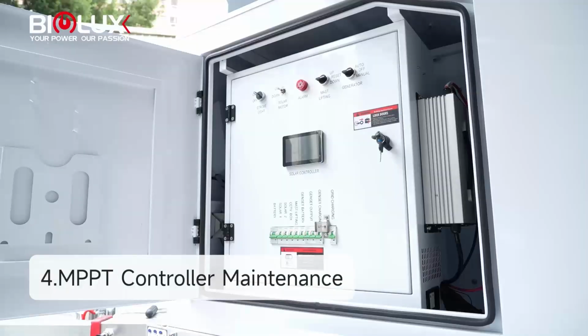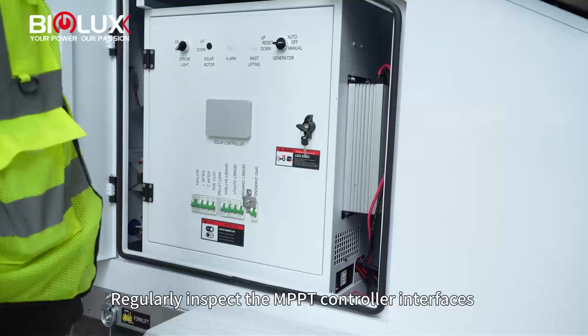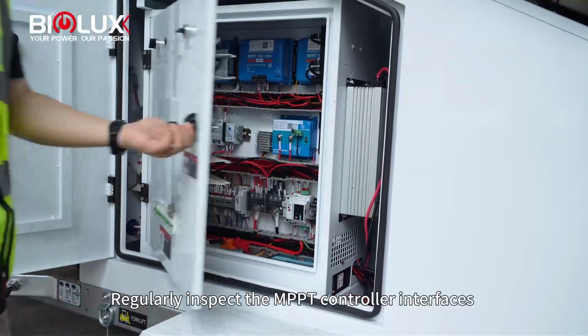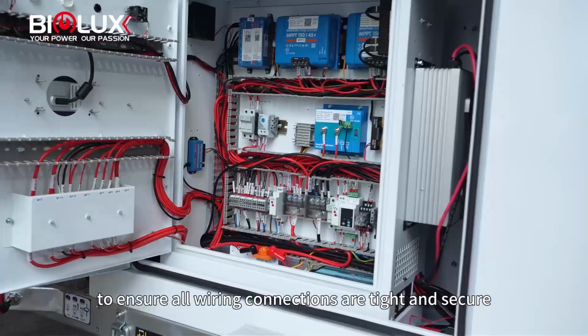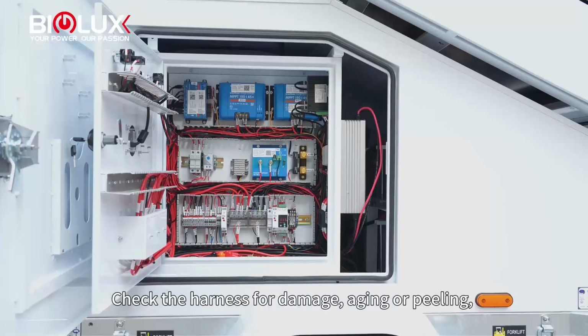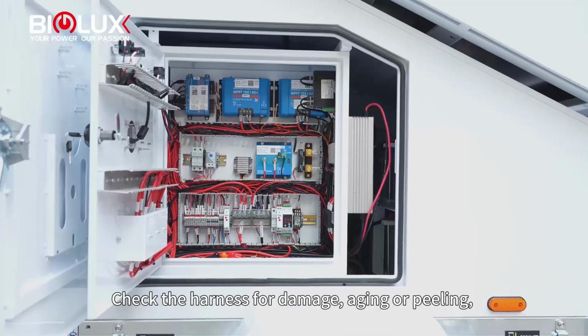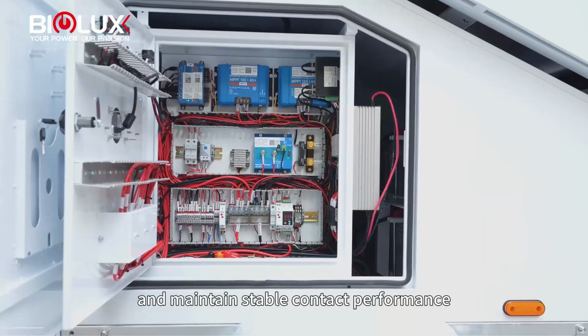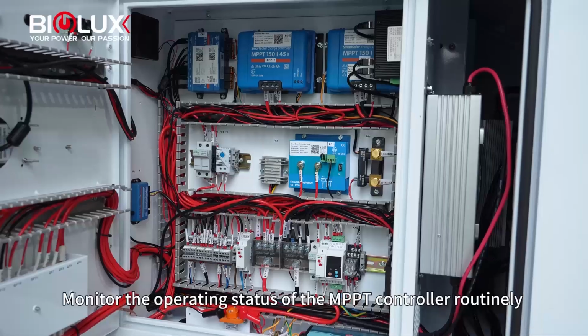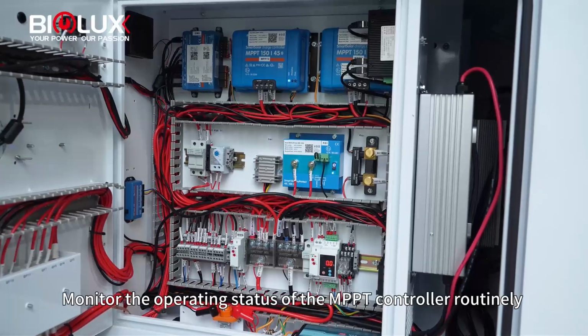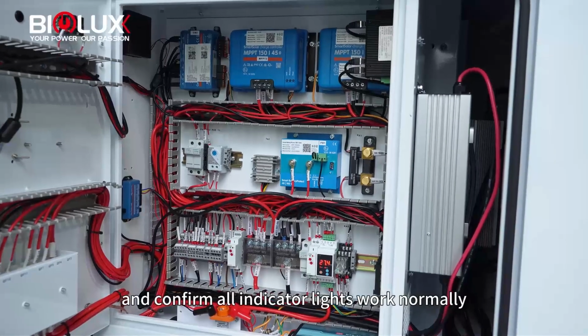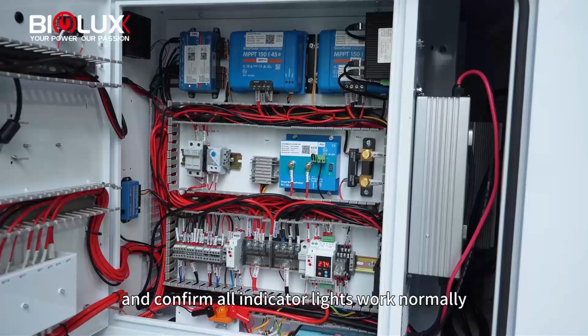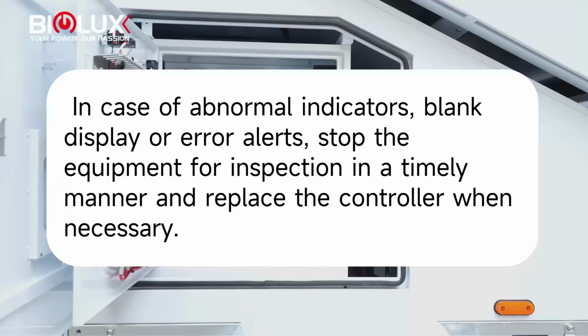4. MPPT controller maintenance. Regularly inspect the MPPT controller interfaces to ensure all wiring connections are tight and secure. Check the harness for damage, aging or peeling, and maintain stable contact performance. Monitor the operating status of the MPPT controller routinely and confirm all indicator lights work normally. In case of abnormal indicators, blank display or error alerts, stop the equipment for inspection in a timely manner and replace the controller when necessary.